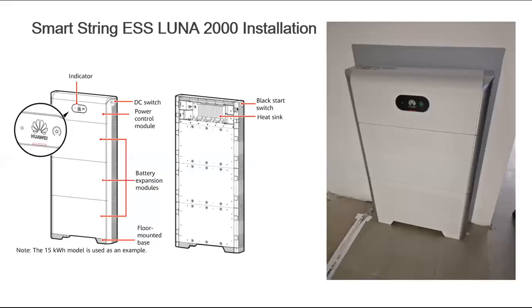Coming back to the installation topic, you can see in the picture a 10 kilowatt-hour battery system installed. On the left side of the screen are the main parameters of the battery - it has LED indicators, you don't see any LCD screen. It comes with LED indicators which give you alarms and the status of the battery. You have DC switches on the right side. The first part is the power control module, then the three battery expansion modules. You can install the battery floor mounted or as a wall mounted solution. On the back side of the battery you will find heat sinks, used to dissipate heat generated from the internal components of the power control module.